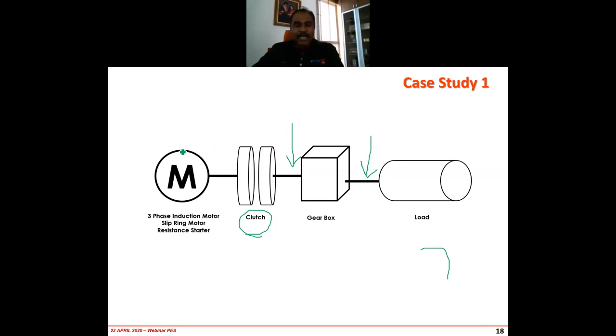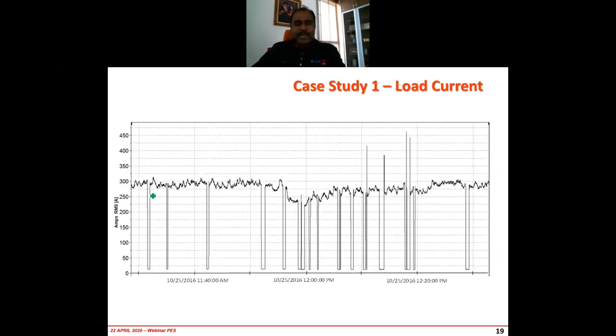So if you are having this kind of system, the question I want to throw to you is, should we go for a variable speed drive? Initially it was not connected to a variable speed drive, but should we go for one? That's a question. Now, we actually measured the current for this particular system. It is drawing approximately 290 amps. Sometimes it drops, but it's always above 200.